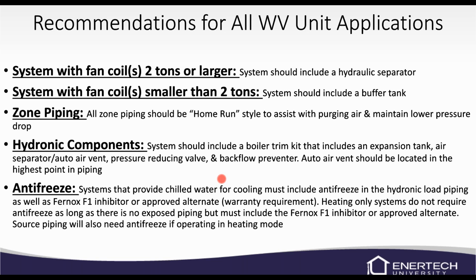We recommend all piping be home run style to assist in purging of air and less pressure drop and easier to service. The system should include a boiler trim kit that includes an expansion tank, air separator, auto air vent, pressure reducing valve, and backflow preventer. The auto air vent should be located in the highest point of the piping.